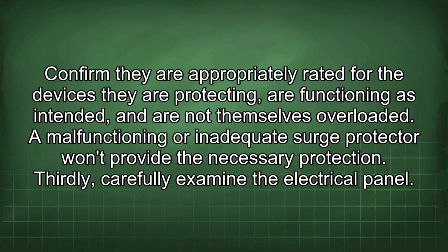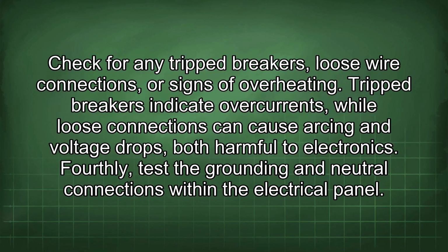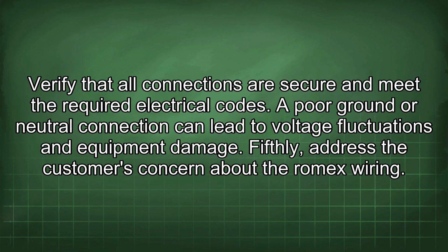Thirdly, carefully examine the electrical panel. Check for any trip breakers, loose wire connections, or signs of overheating. Trip breakers indicate overcurrents, while loose connections can cause arcing and voltage drops, both harmful to electronics. Fourthly, test the grounding and neutral connections within the electrical panel. Verify that all connections are secure and meet the required electrical codes. A poor ground or neutral connection can lead to voltage fluctuations and equipment damage.